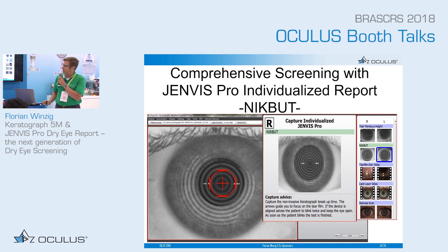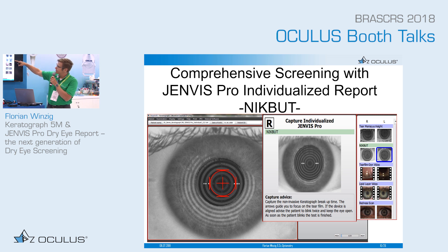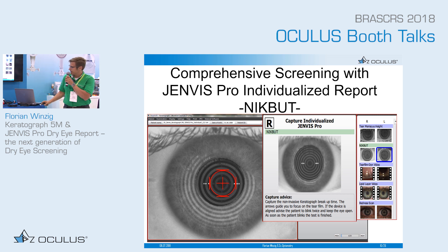The technician just aligns the device to the patient's eye, advises them to blink twice, and then the software automatically starts the NIBUT measurement. A new feature is that the software automatically guides you to the next measurement. For example, you begin with tear meniscus height on the right side, then move to the left. For NIBUT you stay on the left side first, then do the tear film dynamic and lipid layer on the left side, before moving to NIBUT on the right. This minimizes unnecessary movement of the device.